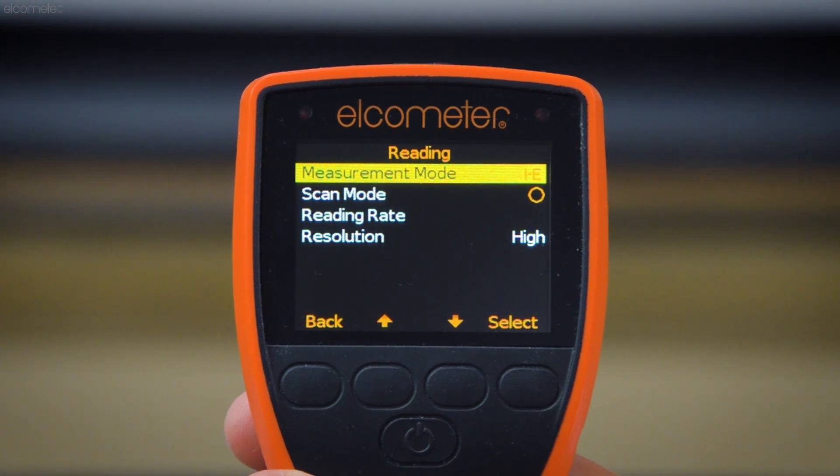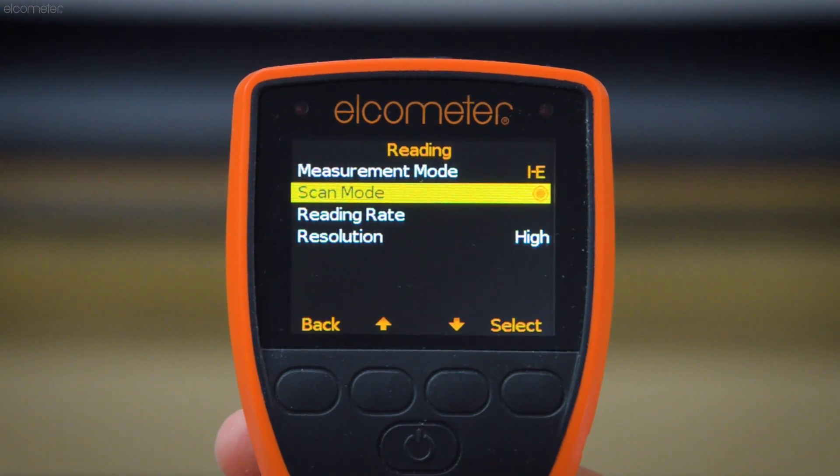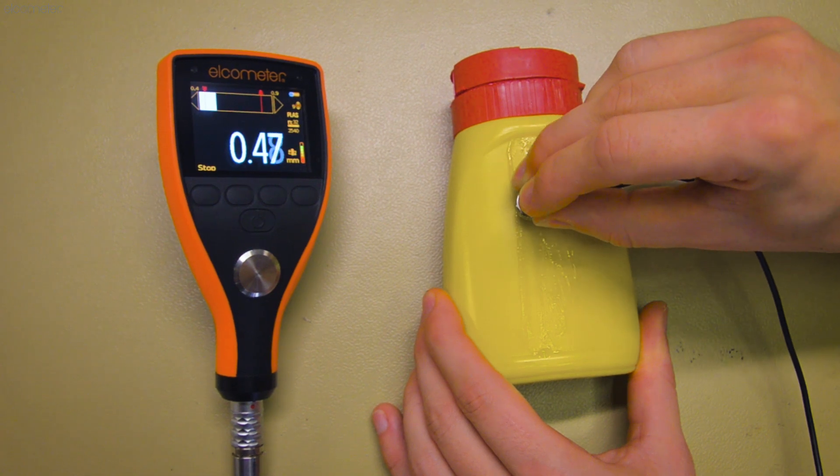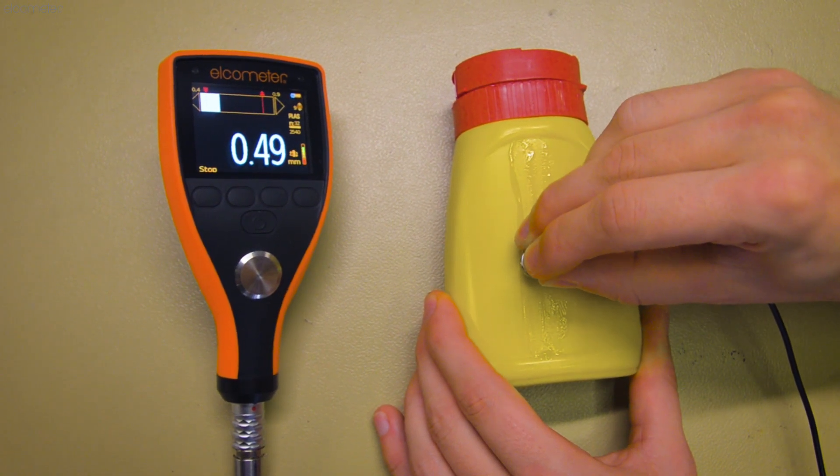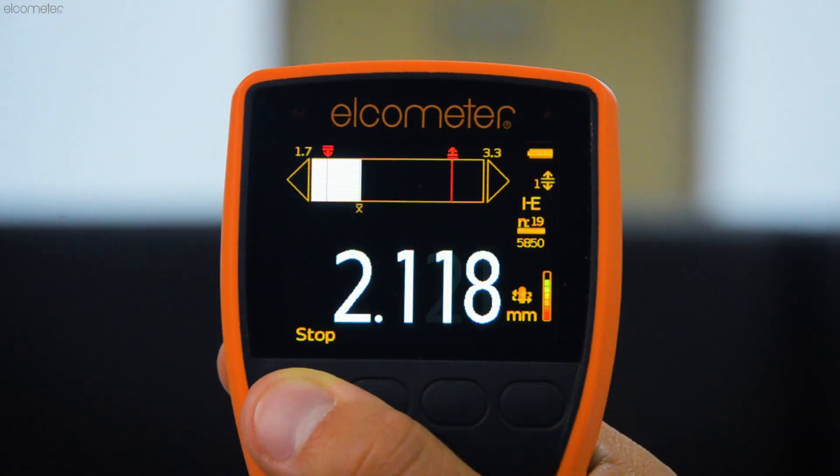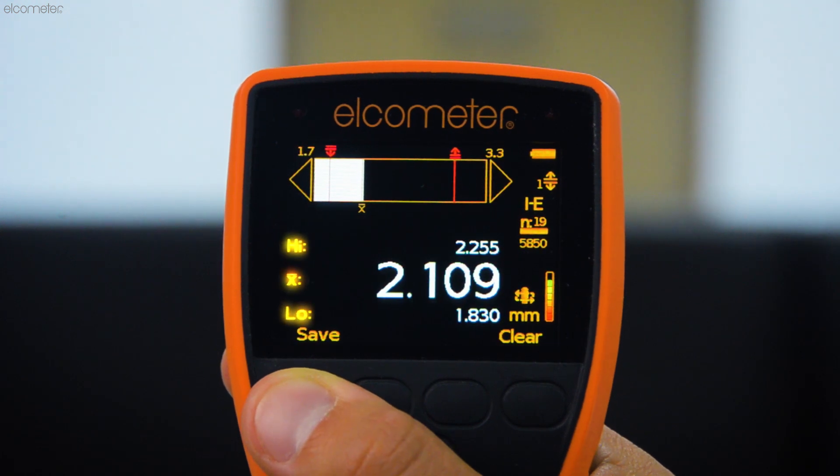Alternatively, the top of the range Elcometer PTG-8 has scan mode for checking large surface areas. Simply scrub the transducer over the test area, and the gauge will display the average, lowest, and highest thicknesses across the scanned area.